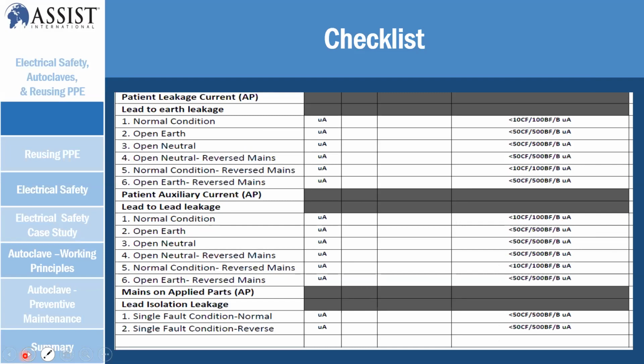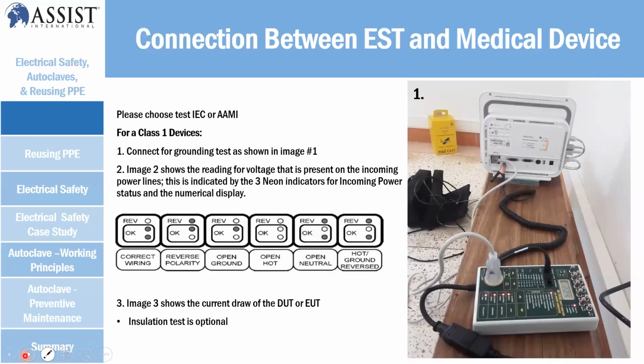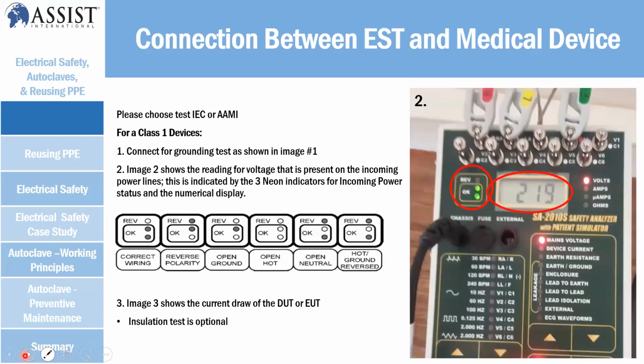Okay, when you make a connection between the EST and a medical device, the first step is always to check the classification of the medical device. Is it class 1 or class 2? And check the type as well. Is it type B, BF, or CF? If it is a class 1 device, you have to do the chassis connection, go to the grounding line, and the power line has to go to the electrical safety analyzer, and plug the main power source into the EST. And you start to check the device by using the display.